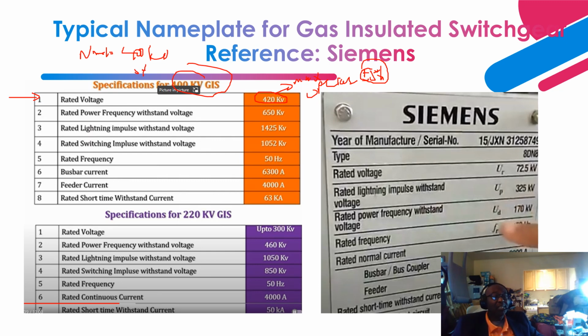So next is the rated power frequency withstand, right here. And what does that mean? If you have an external fault condition, and after the fault clearing, there's an overvoltage, a power frequency voltage. This is the withstand capability of the GIS: 650 kV.